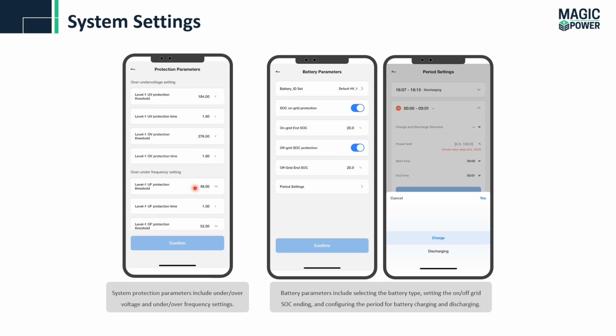Similarly, for the frequency, minimum and maximum frequency, and the time. For example, if it detects the protection threshold value, when it should be disconnected and how long it should take, for example, 1.6 seconds. Battery parameters for on-grid and off-grid SOC protection: we choose 20% for both. It could be 10%, 15, or 20, 30, any value. For period setting, we choose the timing for charging and discharging our batteries. Again, it is for the peak and off-peak timings, like peak and valley prices.